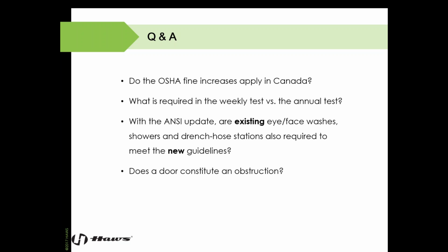With the most recent ANSI update, are our existing eye face washes, showers, and drench hoses required to meet the new guidelines? There is no grandfather clause in the standard. As the standard changes and improves, existing installed equipment must follow those changes. No exceptions there. And does a door constitute an obstruction? We touched on that a little bit, but from the standard, the following verbiage is provided, and I've got it right here with me.